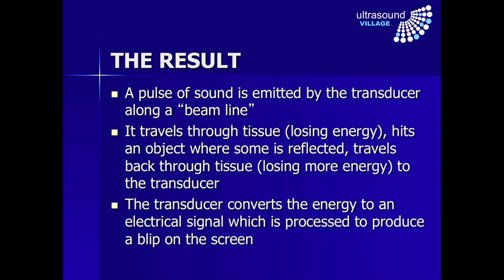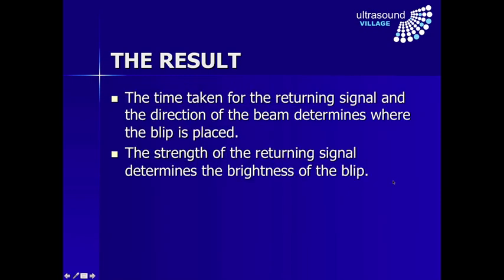In summary: a pulse of sound is emitted by the transducer along the beamline, travels through the tissue losing energy — we call it attenuation — hits an object where some is reflected and most travels through. The reflected wave travels back, gets attenuated a little more, back to the transducer which converts the energy into an electrical signal. The time taken for the returning signal determines how far down the screen the machine puts the blip; the direction of the beam determines where it's placed; and the strength of the returning signal determines the brightness. This is essentially how an ultrasound machine works.